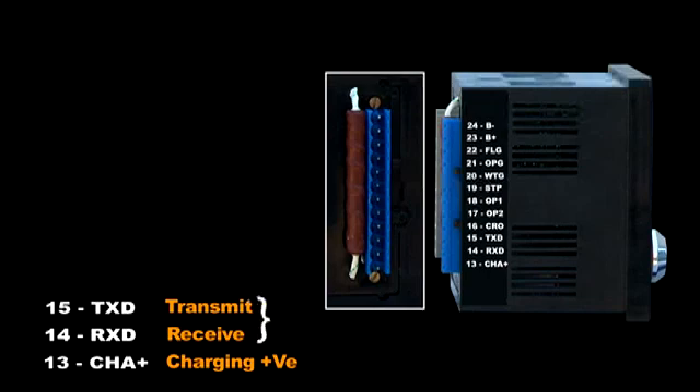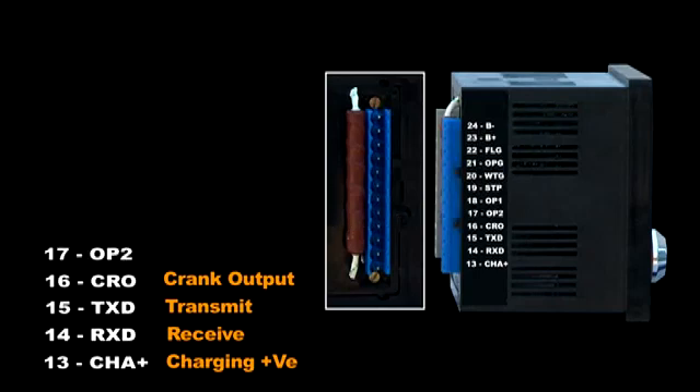The RS232 communication feature is optional. Terminal sixteen is the crank output, connected to the starter motor. Terminal seventeen output two corresponds to fuel level at 40%. Terminal eighteen output one corresponds to fuel level at 10%.